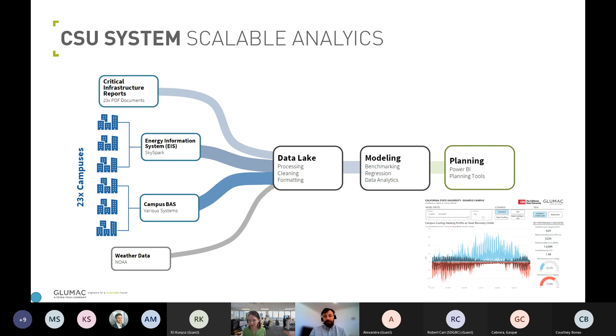For the CSU system, we developed a heat recovery tool. I think there's a lot of really great opportunities of how we can leverage different dashboarding technologies in order to display data and help to inform and understand information. So this shows the cooling and heating profile for an example CSU system. You can see the darker color represents the heat recovery potential. So how much heat can we pull from that campus or from the chilled water and produce hot water? So in this case, we can produce 72% of the heating demand on this campus just based on the chilled water demand. That means we can reduce 70% of natural gas.